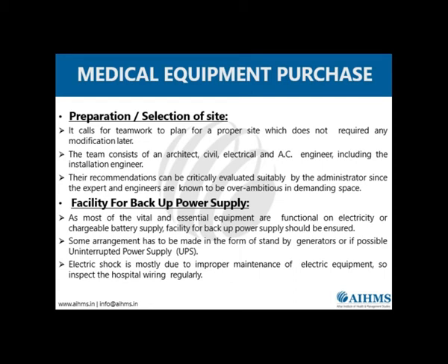Similarly, you require good teamwork to know what will be the site for putting up the equipment and the preparation that needs to be done in advance. Here it requires a team of engineers, which might comprise the architect, the civil engineer, the electrical engineer, and the AC engineer, because equipment like ultrasound machines requires full-fledged AC backup.